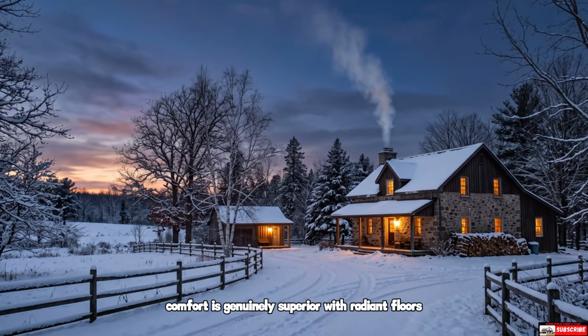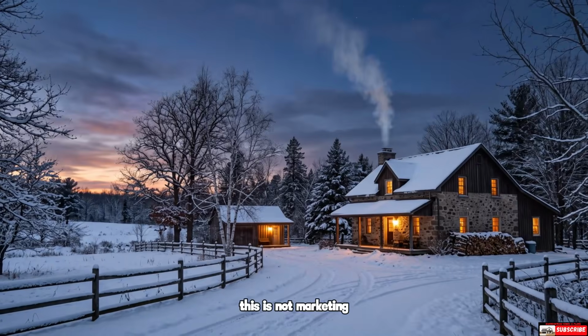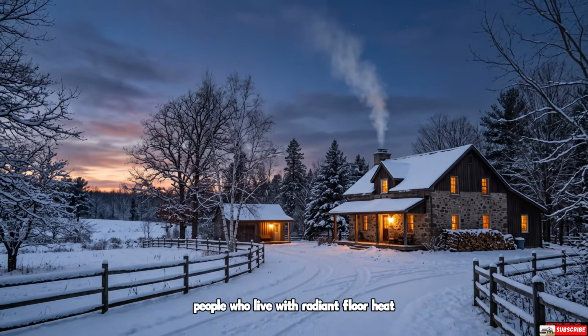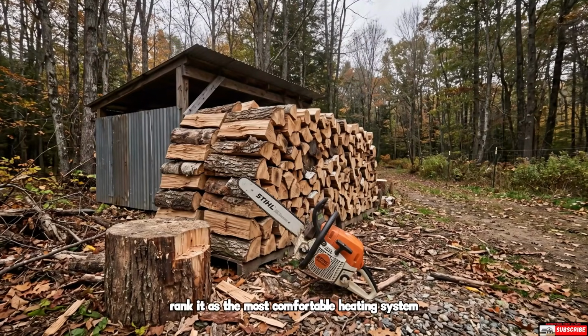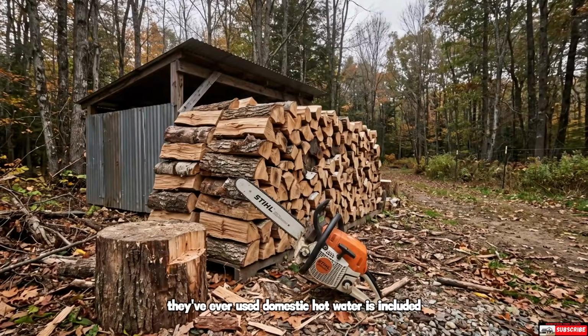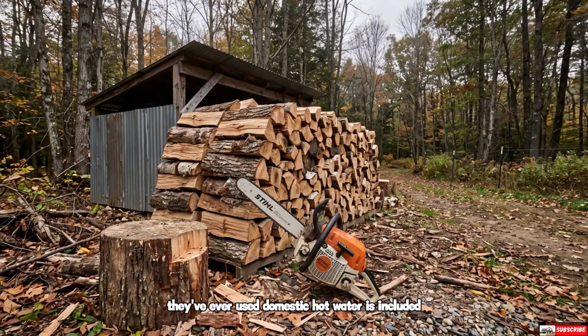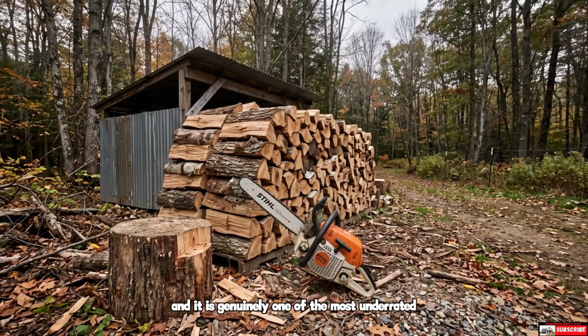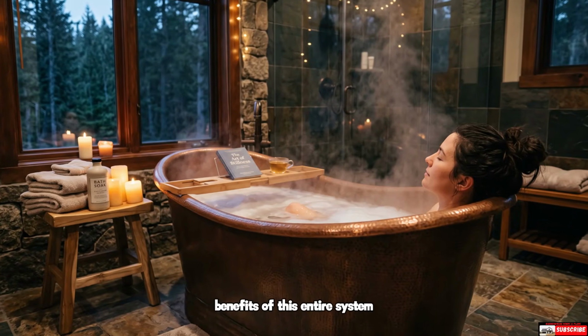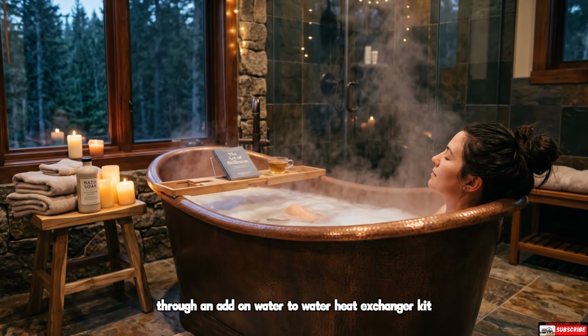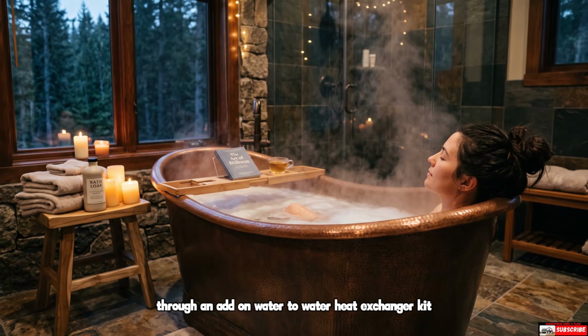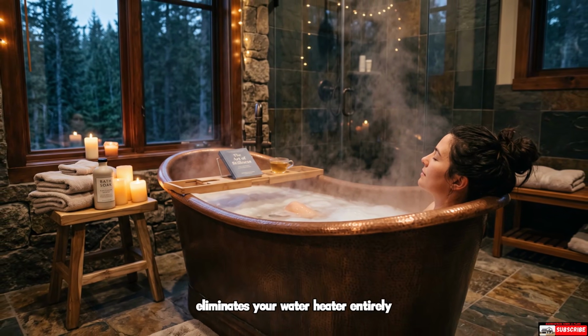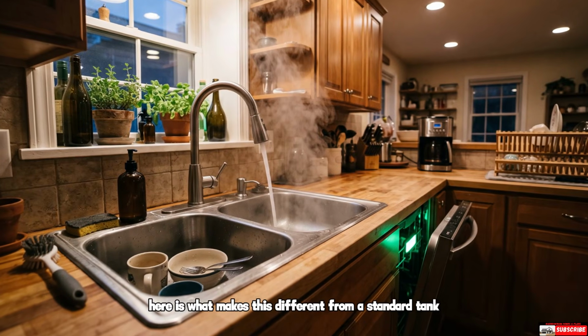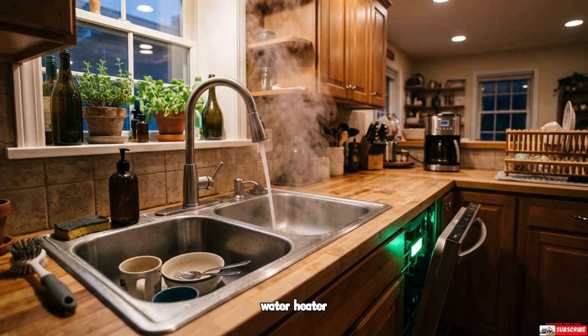Comfort is genuinely superior with radiant floors. This is not marketing. People who live with radiant floor heat consistently rank it as the most comfortable heating system they've ever used. Domestic hot water is included, and it is genuinely one of the most underrated benefits of this entire system. Through an add-on water-to-water heat exchanger kit, your outdoor boiler eliminates your water heater entirely. But here is what makes this different from a standard tank water heater.